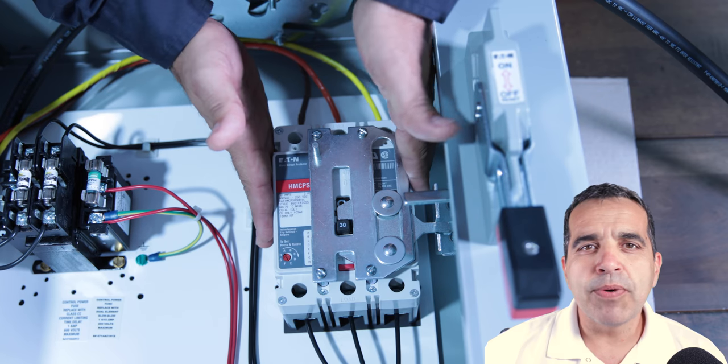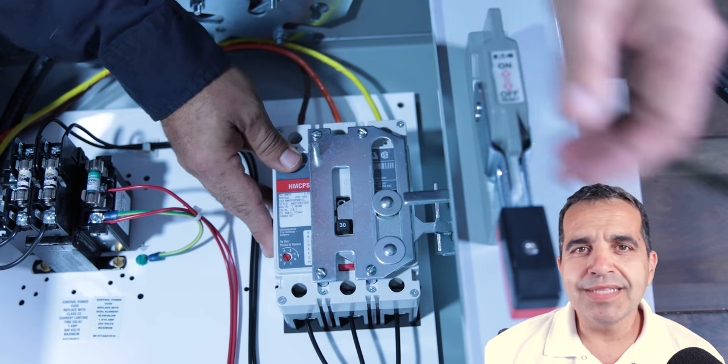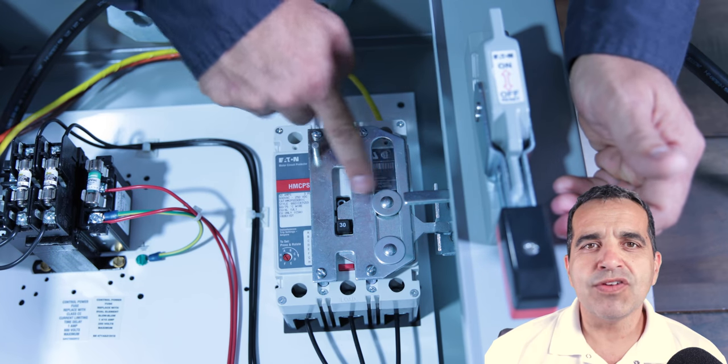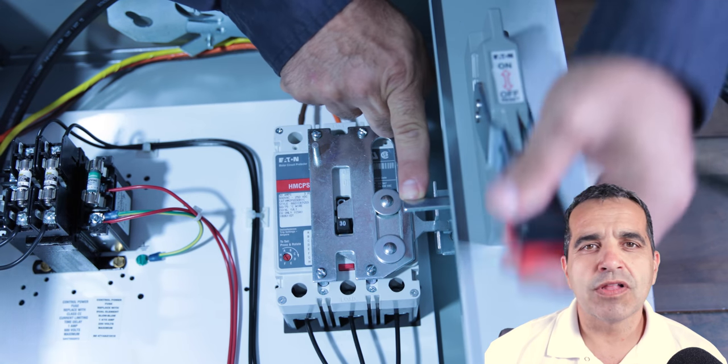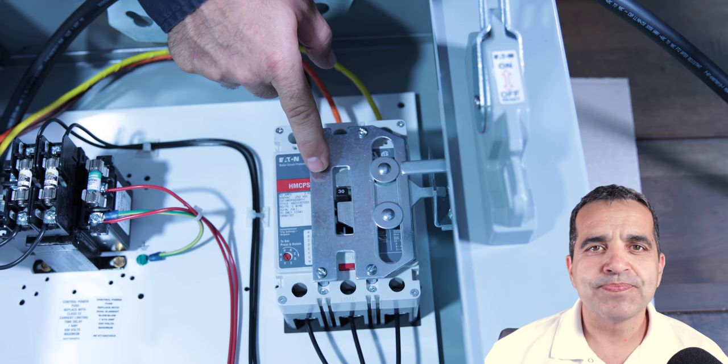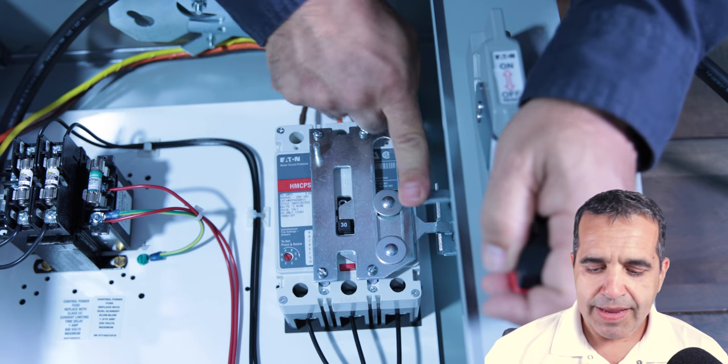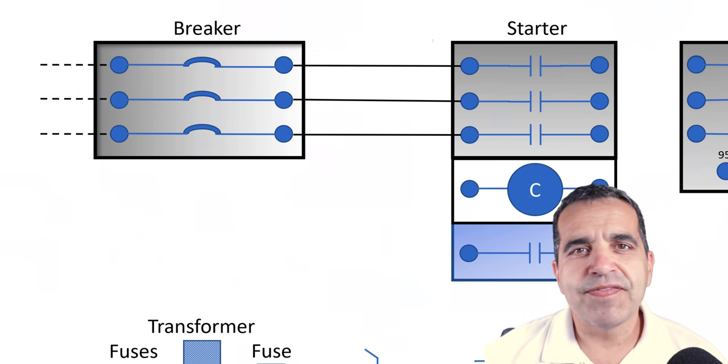The breaker has three contacts. This is a three-pole 480-volt breaker with three normally open contacts. When the breaker is closed, those contacts close. When the breaker is turned off, those contacts are open. Here we're showing our breaker closed, and then that closed breaker is feeding through three black wires.